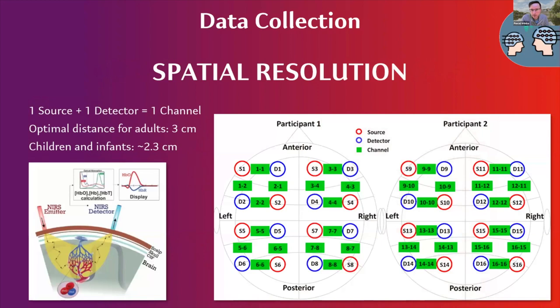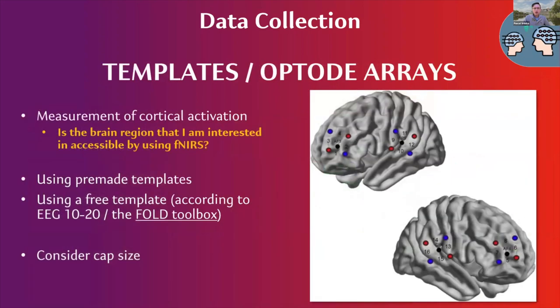Regarding spatial resolution, we usually have about 20 to 30 channels, but these days you can ramp up quite considerably to 50 or 60 channels. We have to ensure channels are about three centimeters apart — for children and infants it's a little less. This means we have to carefully decide on our montage, template, and optode arrangement, as not all arrangements that might be theoretically desired are actually practically possible given how sources and detectors need to be arranged.